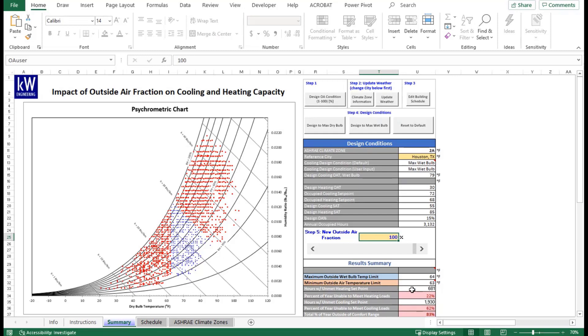These charts here tell you what your unmet hours for either cooling or heating are. At the very bottom here, you have the percentage of the year in which you're not going to be able to meet the load requirements of your building, which at this point at 100% with the original 15% design, you're having about 83% of the year not being able to meet your load.